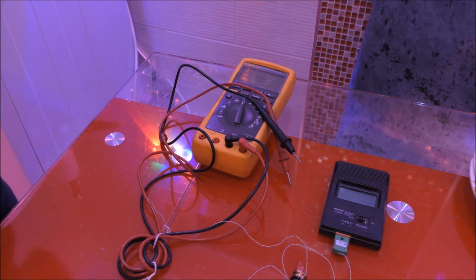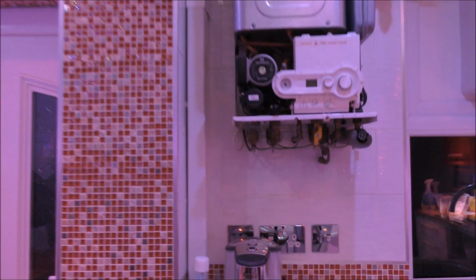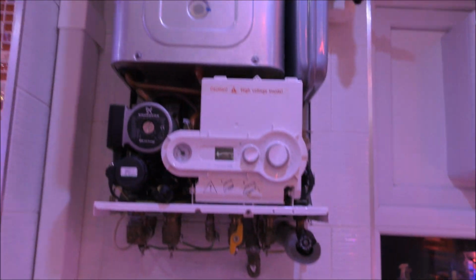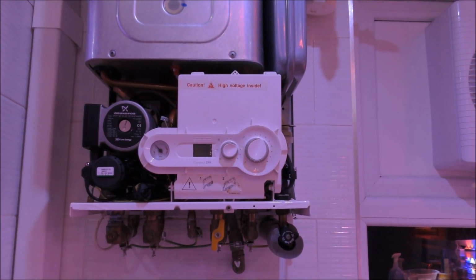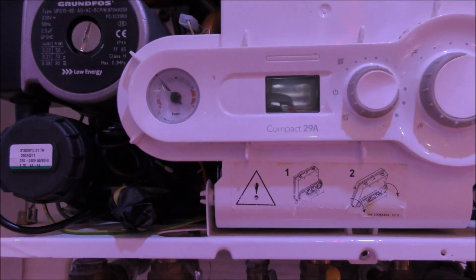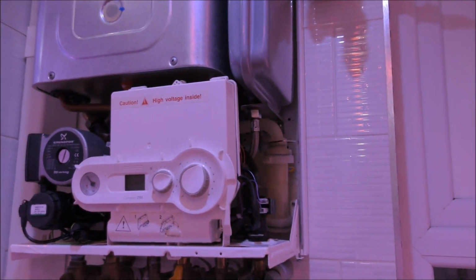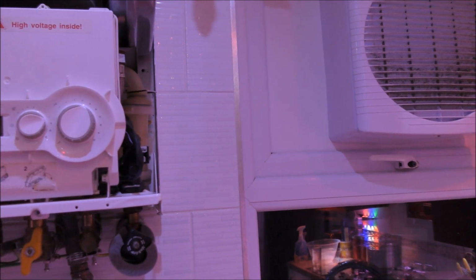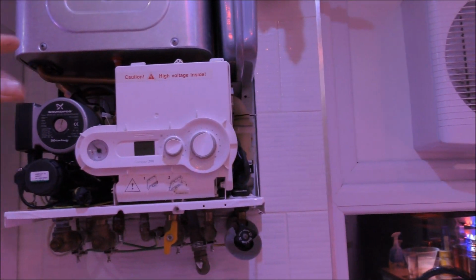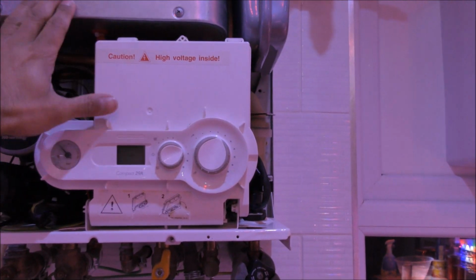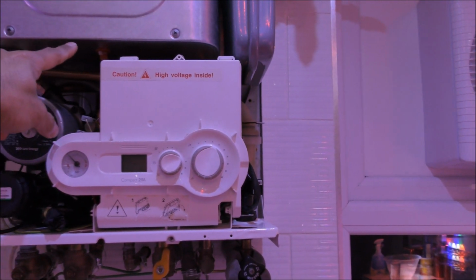So the boiler's working absolutely fine, let me show you. It's been several hours since I put everything back together, and it's working smashing. The pressure's still where it should be. Now you know that when you're getting a knocking, burbly, or popping noise out of your main heat exchanger unit, the culprit is there, the blockage basically.